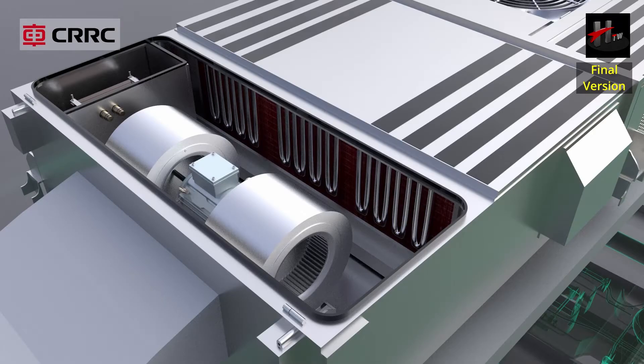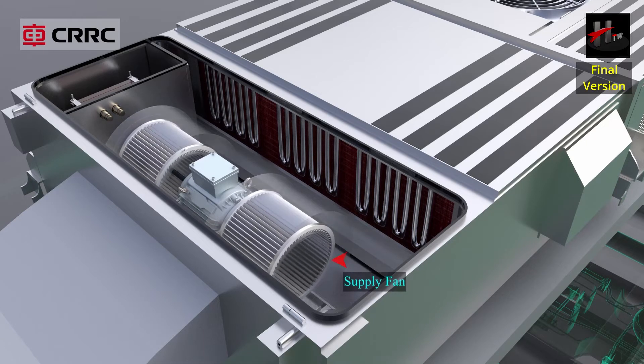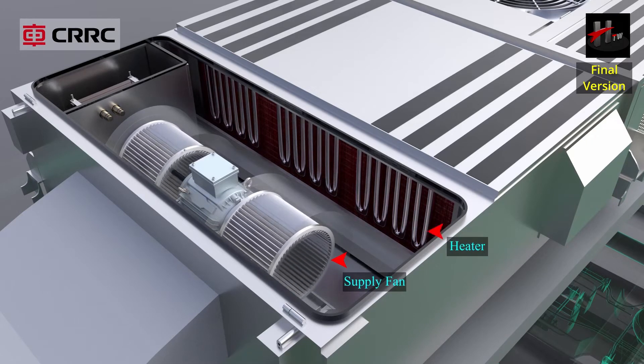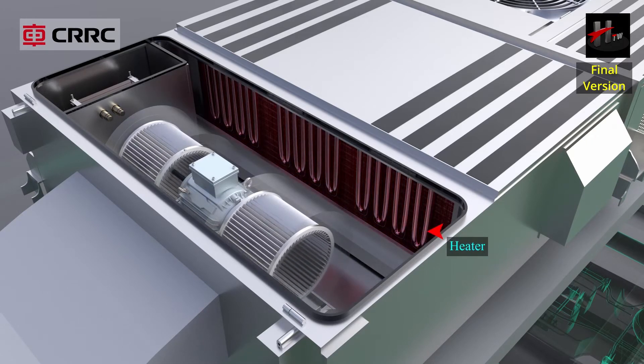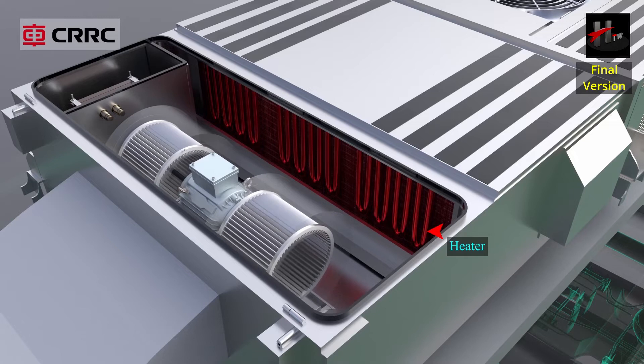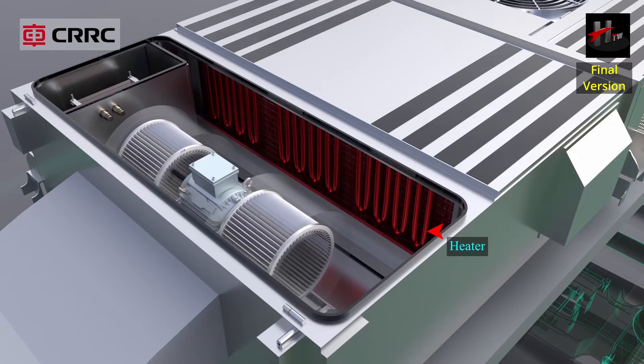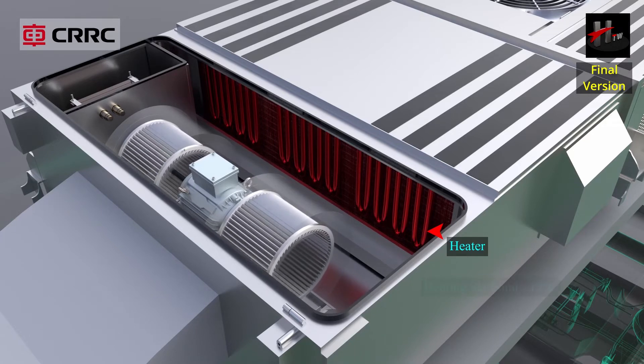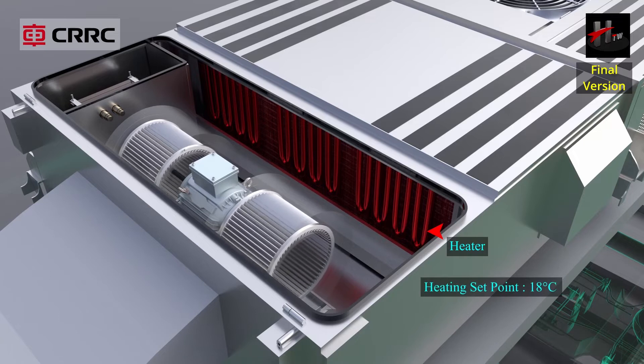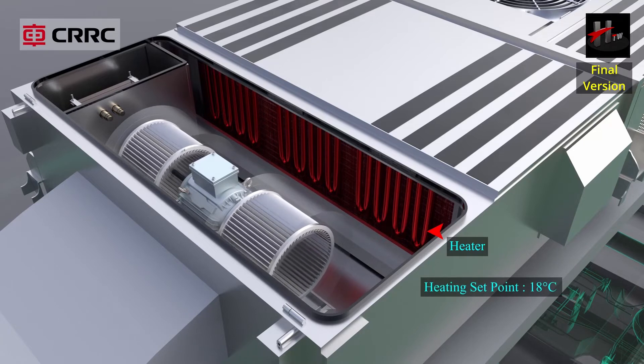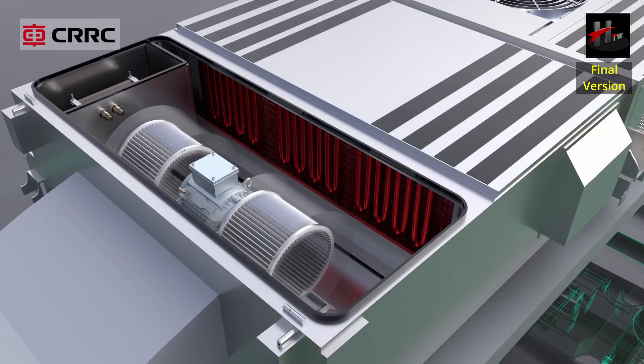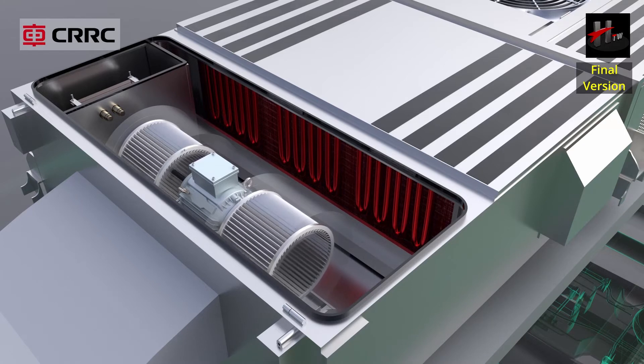During operation in the heat mode, only the supply fan and the heater are energized. The heater bank is energized when the return air temperature falls below the heating set point, i.e. 18 degrees centigrade. The heater banks also get energized in the dehumidification mode.